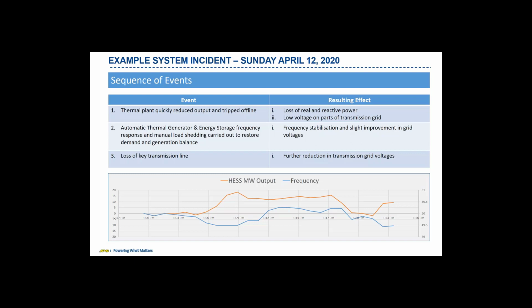The system is set up so that the flywheels act first to handle the minor changes in frequency, because the flywheels are able to manage the heavy cycling without much degradation in their storage capacity. But batteries, on the other hand, the more you cycle them, the more they see a reduction in the maximum capacity they can store, so their lifetime will be lower. So the hybrid system was chosen to give us the benefits of the batteries, but to also use the flywheel for the smaller variations so that we don't have to heavily rely on the batteries.